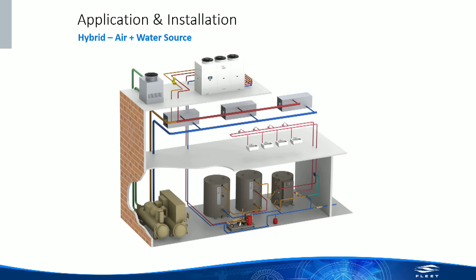Or more traditionally, if you have a condenser water system in a building where you're only running air conditioning, say it's an apartment, you're only running air conditioning in the summertime, and you no longer have that rejected heat during the winter, you can run this as a water source unit, take advantage of the higher COPs during the summer when you have all this rejected heat, decrease your cooling tower loads, and then come the winter time, run it as an air source unit to still provide domestic water to the building.